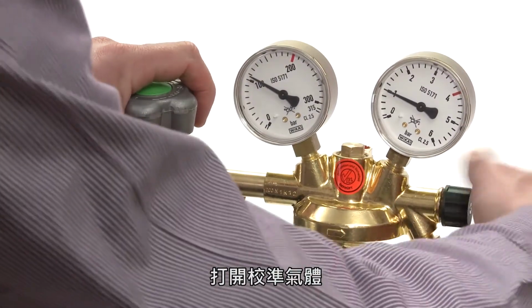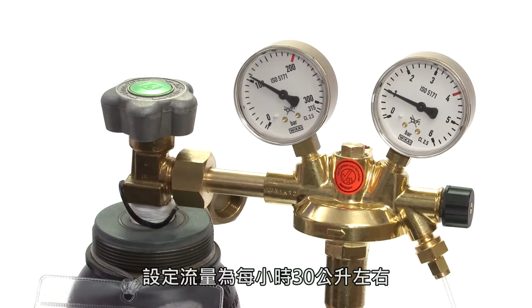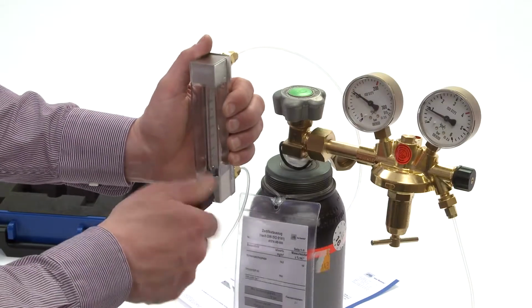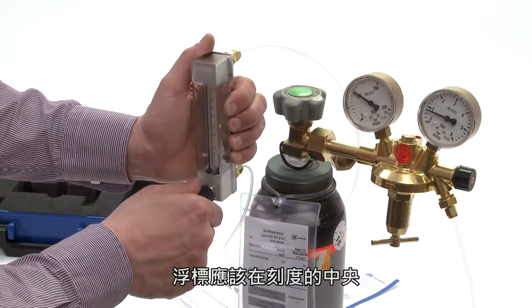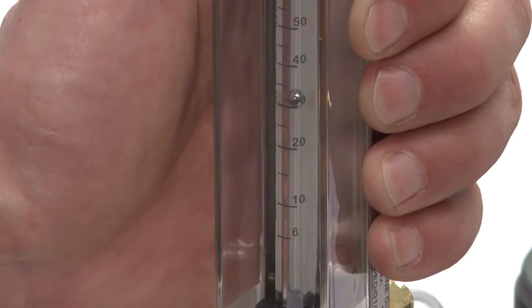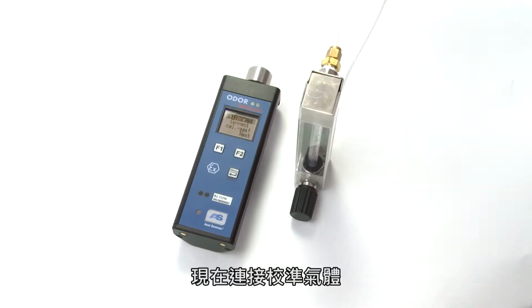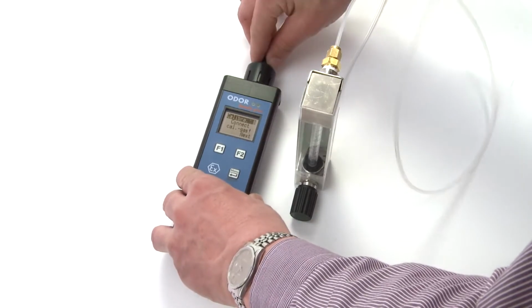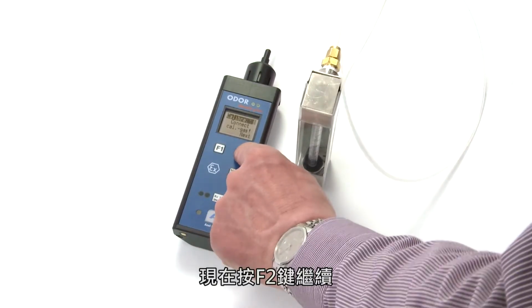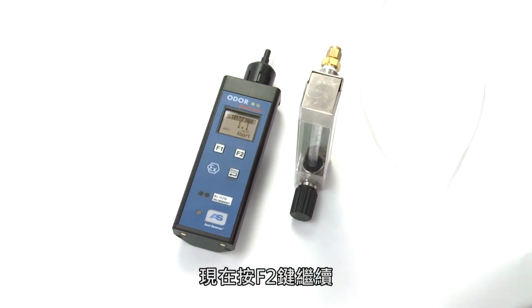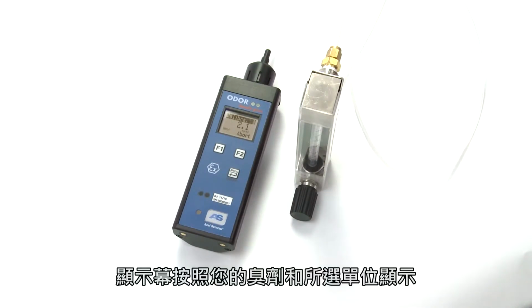Open the calibration gas and set the flow to approximately 30 liters per hour. The floating body should be in the middle of the scale. Now connect the calibration gas. Now press F2 to continue. You see the display advance.